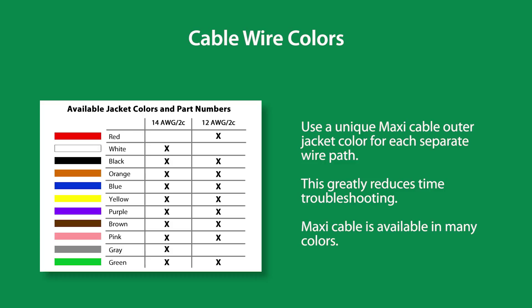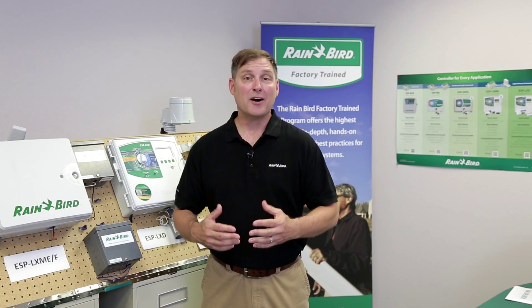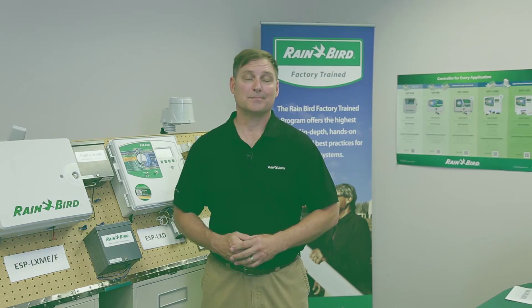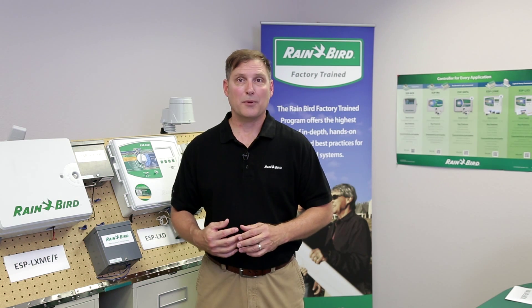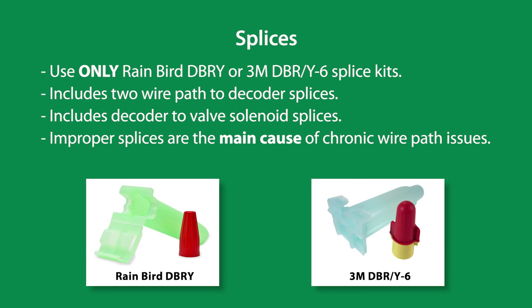Maxi cable is available in many colors. Moving on to splices: to qualify as a 100% Rain Bird specification compliant splice, only Rain Bird or 3M direct burial splice kits are used for all splices. This includes splices from the two-wire path to decoder and decoder to the valve solenoid.